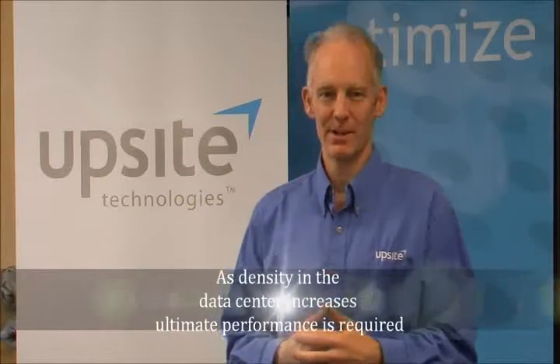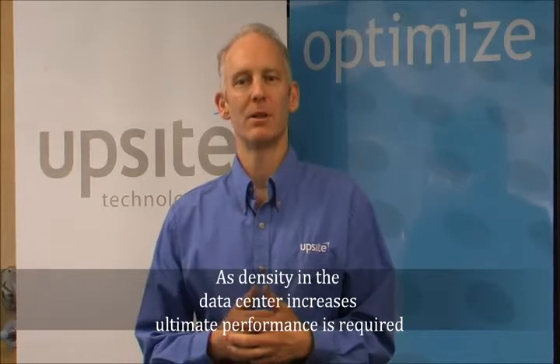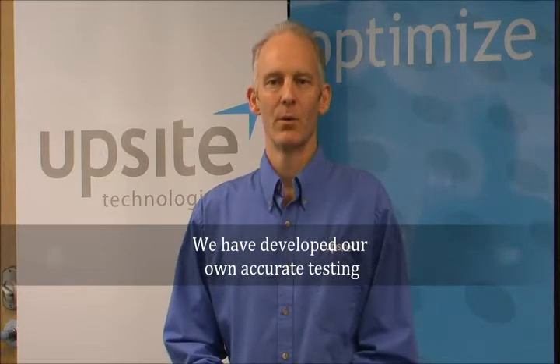The ultimate performance metric of a raised floor grommet is its ability to sustain differential air pressure with minimal leakage. At Upsite, we test all of our products to benchmark leakage performance and use extensive leakage testing in the development of all our products. Measuring low airflow rates and low pressures is not easy, so we developed a specially engineered leakage testing device which uses a device called a Thomas meter.